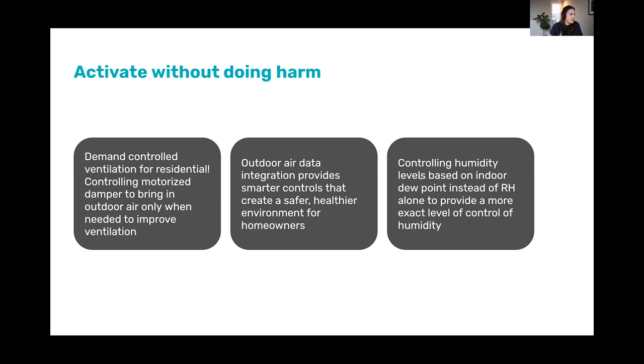And essentially what we want to do is activate the equipment without doing harm. So this idea of demand control ventilation for residential, we've got that controlling of the motorized damper to only open when needed. And this is where our basis is: it can be installed complementary with any ASHRAE 62.2 standards. We're ensuring, or a system like this should ensure, that the home is responding to events throughout the day so that we have more ventilation when we need it, and then we can fall back to the standard if that's what you've designed into your system. I just spoke again to the outdoor air data, so we're trying to make it a safer environment.